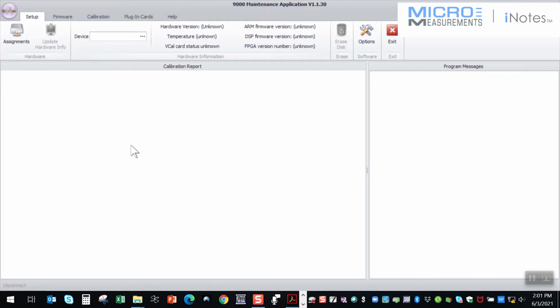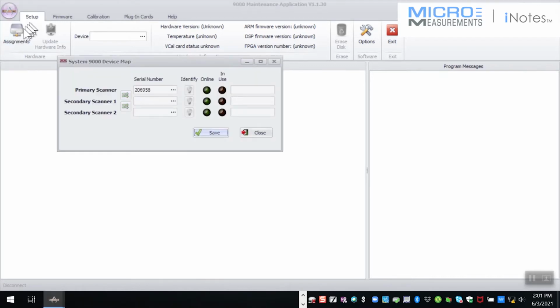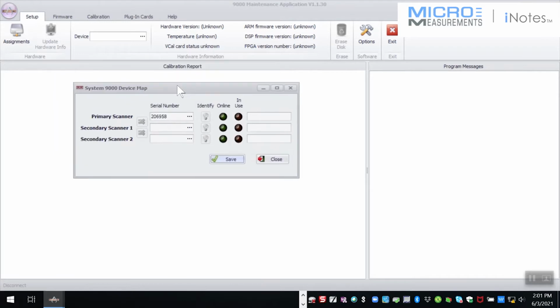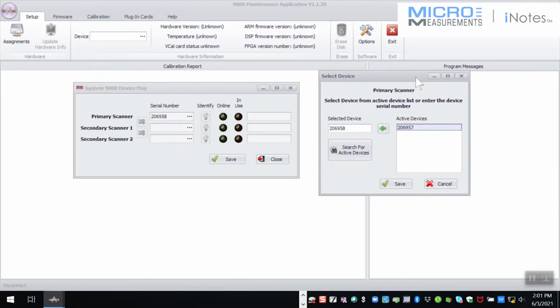plugged into the scanner. Paul, I guess you want to go ahead and get it talking? Yeah, let's see if we can find it, because right now it doesn't seem to have a device. This first button under setup, it says devices, and by default it's finding a serial number of some scanner, but it's not showing any connectivity to it. My green light button that I expected to say online is not there. So what I'm going to wind up doing is checking the manual. It's going to tell me to hit these 3 dots right here, which opens up another window. And even before I get to hit that button, it did a search and it found a scanner.